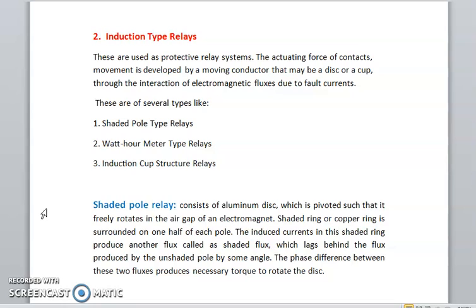Induction type relays. These are used as protective relay systems. The actuating force of contacts movement is developed by a moving conductor that may be a disc or a cup, through the interaction of electromagnetic fluxes due to a fault current. These are of several types like shaded pole type relays, watt-hour meter type relays, and induction cup structure relays.